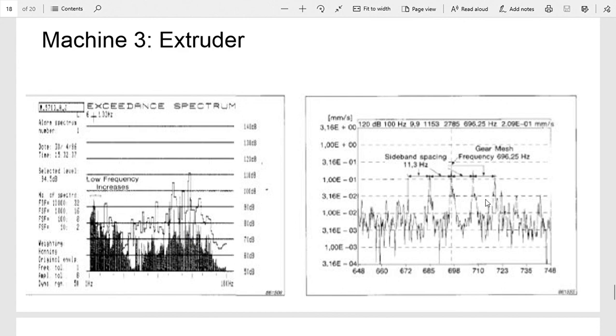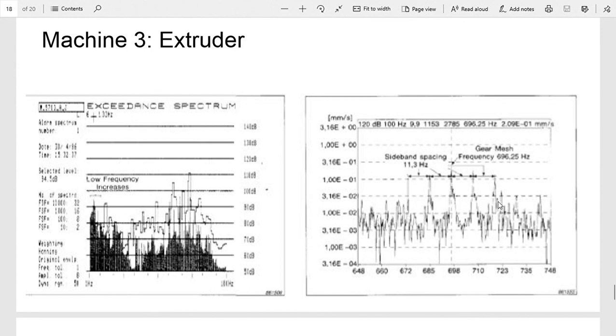And lastly, this is a gear teeth plot. So your gear mesh frequency was at 700 hertz, and then at each of these spikes the sideband spacing is from the shaft speed. When they stripped this gearbox, they found that there was damage to one of the teeth on the gears, which was causing these spikes.